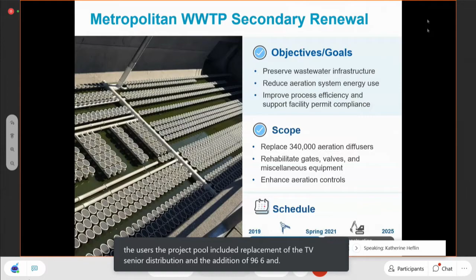The project shown here will replace 340,000 ceramic air diffusers within the aeration tanks with membrane diffusers. It will include replacement of the PVC air distribution piping and the addition of 96 six and eight inch air control valves to enhance aeration control. The project will also rehabilitate the tank under-drain piping and meter vaults.